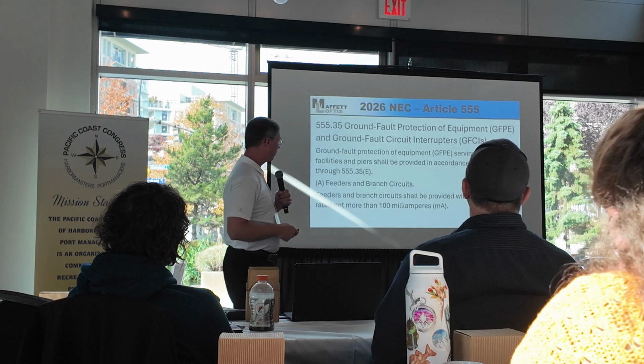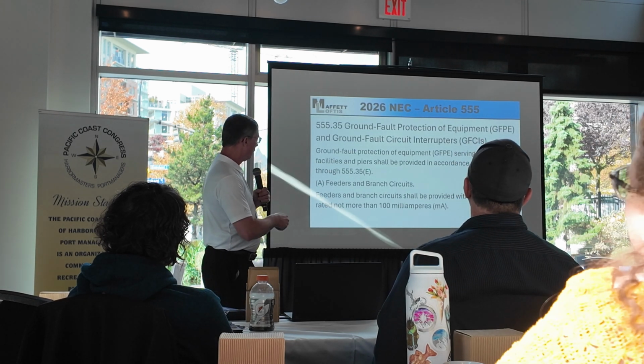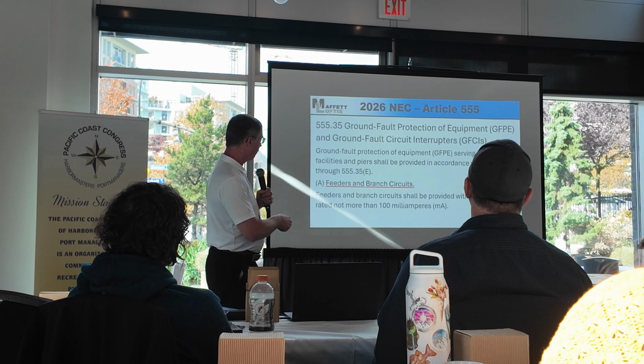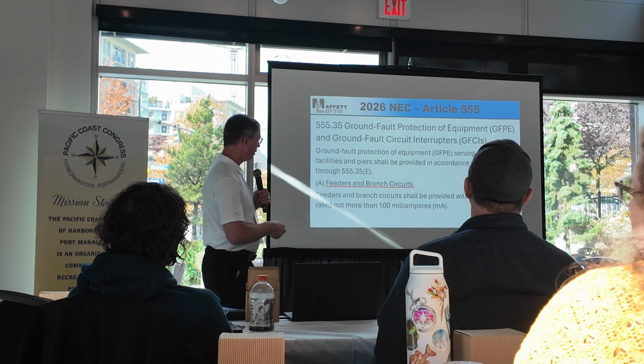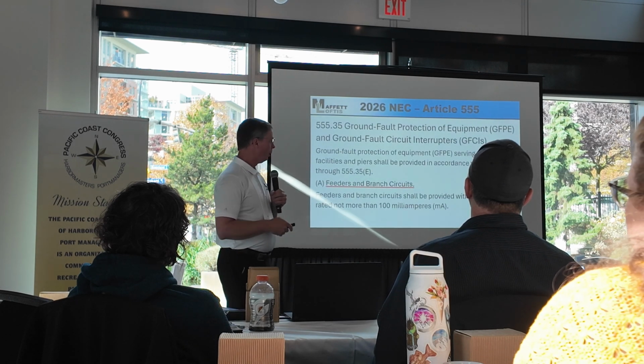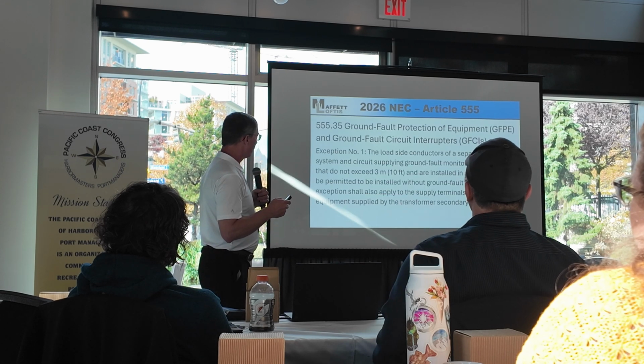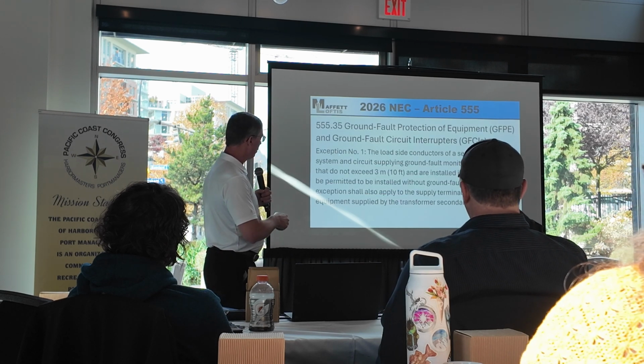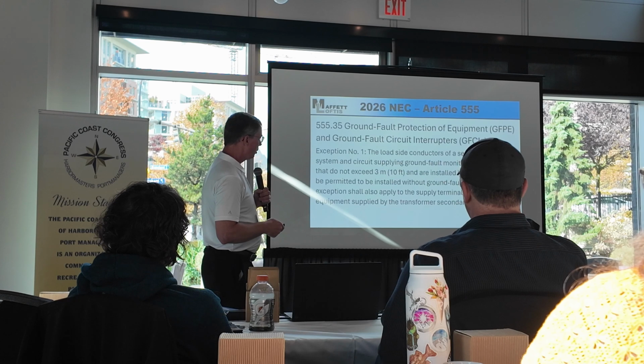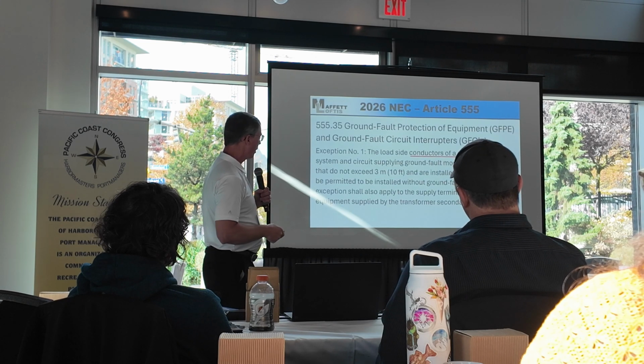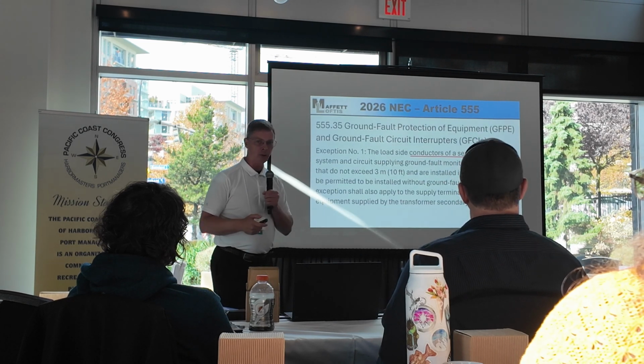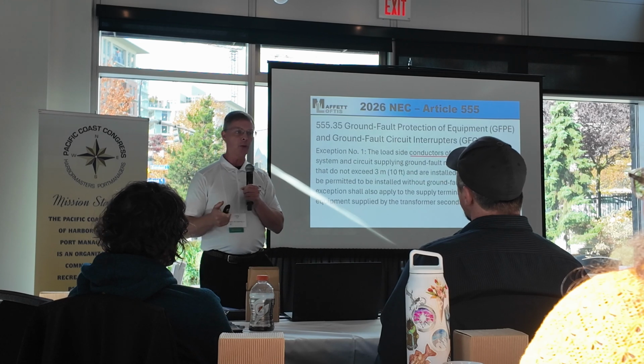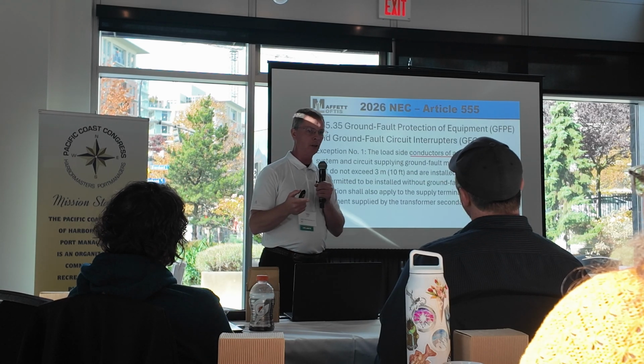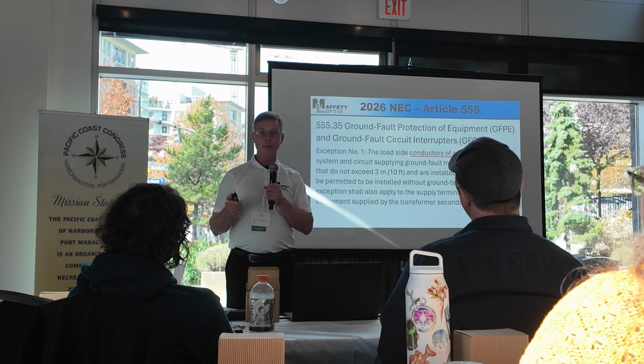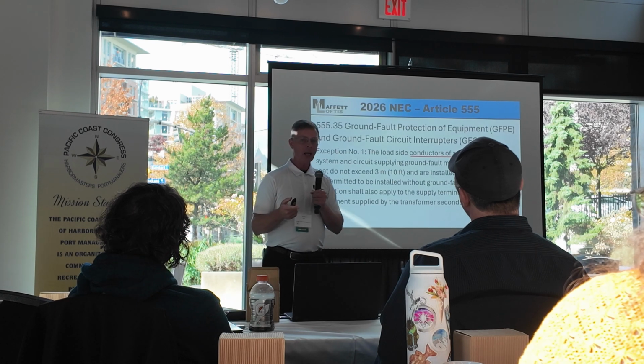This is Article 555.35, and it's where GFPE is required for feeders and branch circuits at not more than 100 milliamps. And the reason I'm doing this is because there's an exception that says that conductors of a separately derived system do not require GFPE. And that separately derived system can be the secondary side of a transformer. It can be a battery inverter.